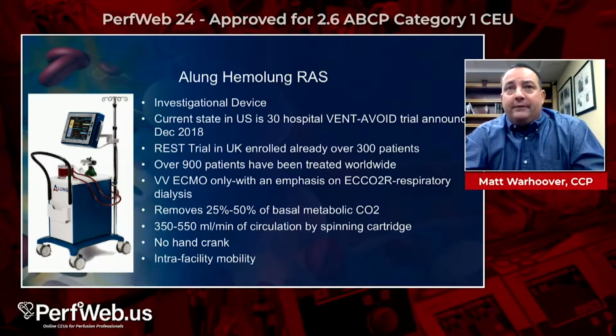It removes between 25 and 50% of your basal metabolic CO2. The cartridge inside of it almost looks like a cell saver. I want to call it an oxygenator. They call it a respiratory dialysis cartridge, but for all intents and purposes, it is an oxygenator. It just doesn't oxygenate as well as it should if you compare it to the other ones. It stands stationary in the device, and the cartridge inside spins. There's just a constant blood in, blood out of a single pass, and the cartridge just spins within it.